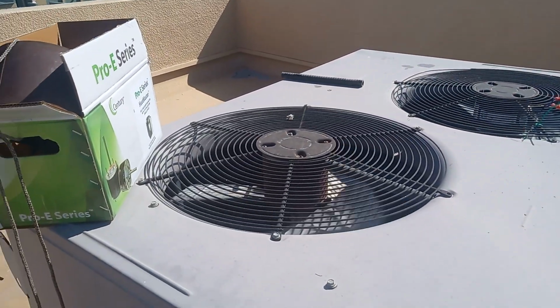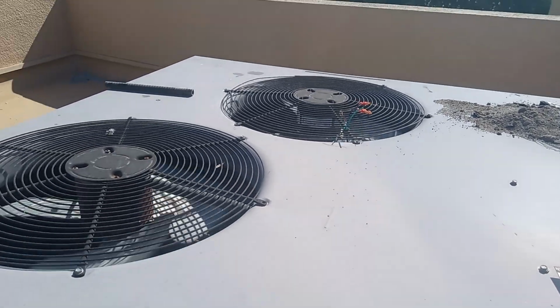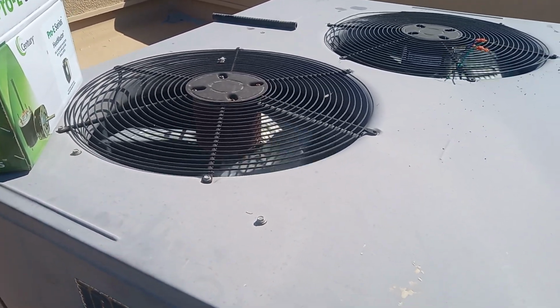The vertical ladder takes me about halfway. I've got another ladder propped up against it. There's the replacement fan motor. This thing had multiple problems. The fan motor was bad, and I think it's been out for a while. It's been turning at 1200 RPM, but there's just a weird strobe effect with the camera.